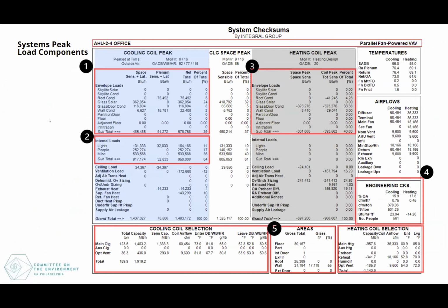So this is a trace report of a typical system. It's called system checksums in a trace report. And as you can see, there is the cooling peak and there's the heating peak. All these are envelope related loads. These are internal loads. And you can see that the internal loads are all zero in the heating peak.